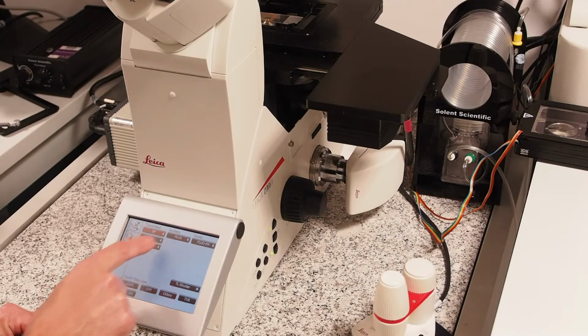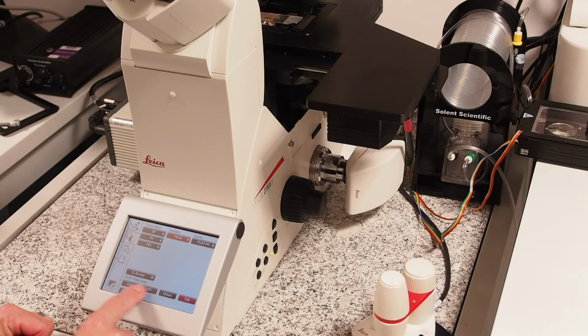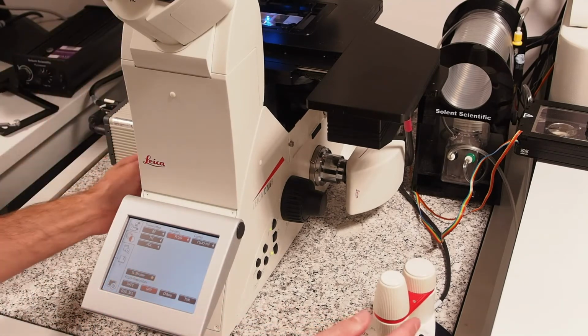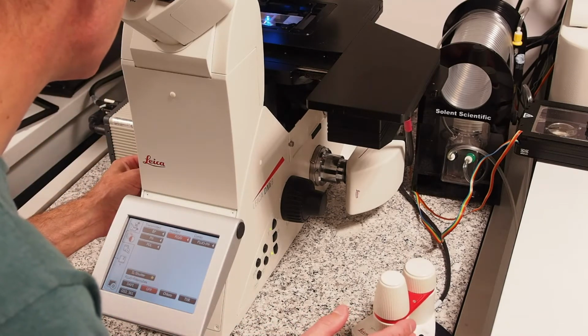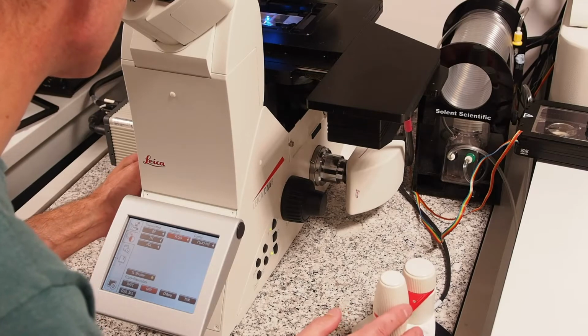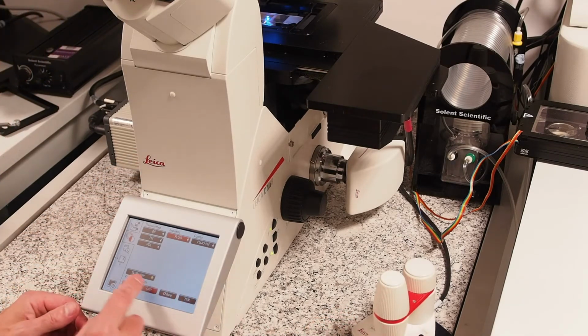If you want to visualize using fluorescence, select the fluorescence button within the Contrast tab and choose your appropriate filter cube from the selection at the bottom of the screen. A list of these filters is written on the wall opposite the microscope. Open the shutter using the instant light shutter button. Once you are finished, turn off the shutter so you don't bleach your sample.